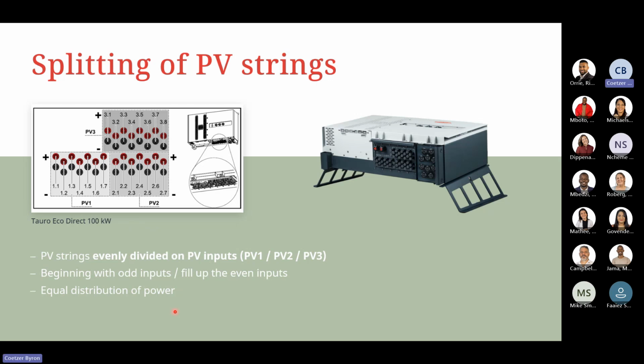Next, and importantly for the Fronius Tauro, is what we call the splitting of the PV strings. Your PV strings need to be evenly divided across your PV inputs, PV1, PV2, and PV3. If it's 12 strings in total on the unit, we need to make sure we have 4 on PV1, 4 on PV2, and lastly 4 on PV3. We need to make sure we evenly divide the strings as best as possible.